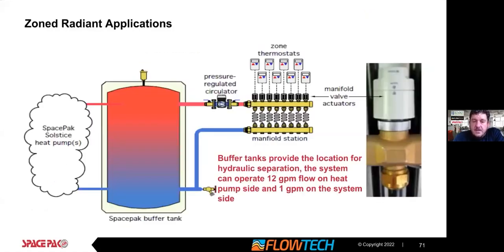applications. In this application, it's a radiant floor heating with the actuators, zone thermostats, and actuating a manifold here. And once again, this is the critical buffer tank function, to decouple that flow rate. You still need 13 gallons a minute in your SpacePak unit, but maybe it's just the master bathroom that's calling for heat, and so you've got a 1 gallon a minute need on the system side, and the buffer tank is what's managing all that. And without that, the systems won't work.